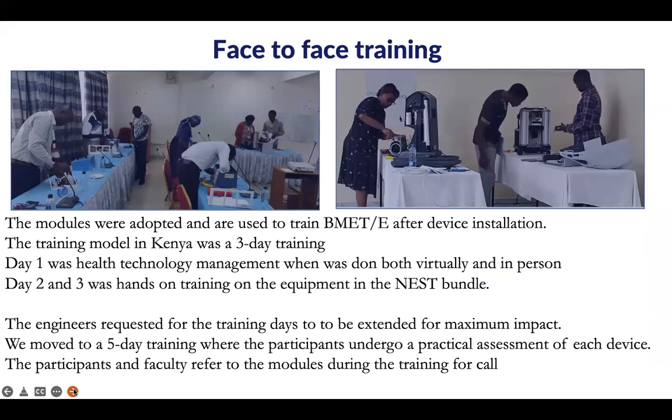So for face-to-face training, as I mentioned earlier, the training model was 3 days, and day 1 was technology management, where we found a gap, and days 2 and 3 were hands-on training. But as feedback, we changed to 5-day training, and we've done 2 of the 5-day trainings where we do practical assessment on each device.